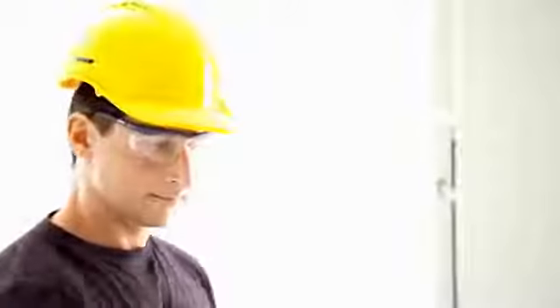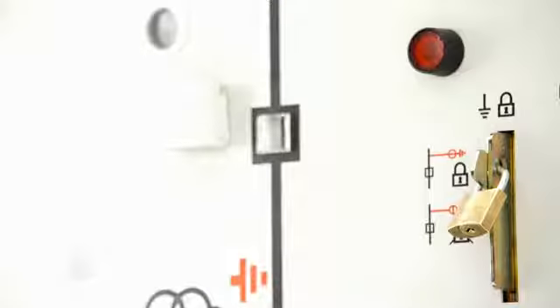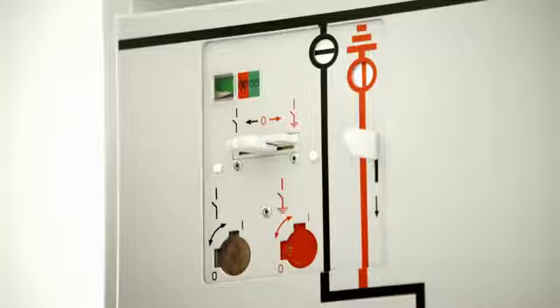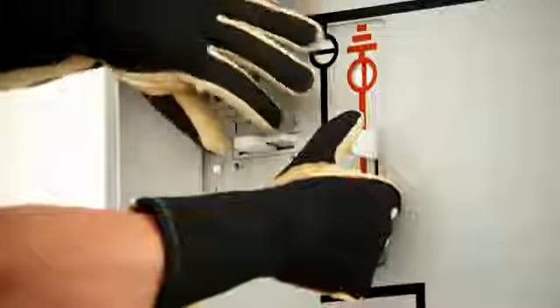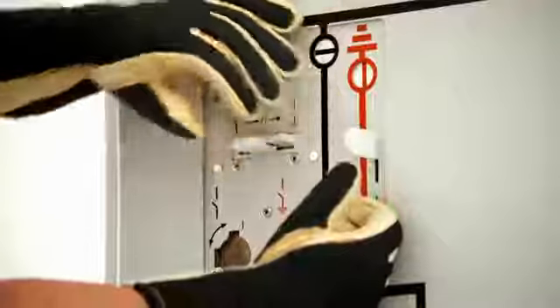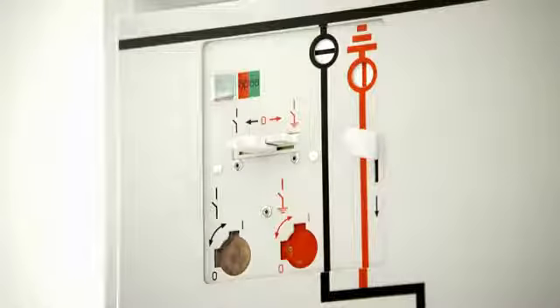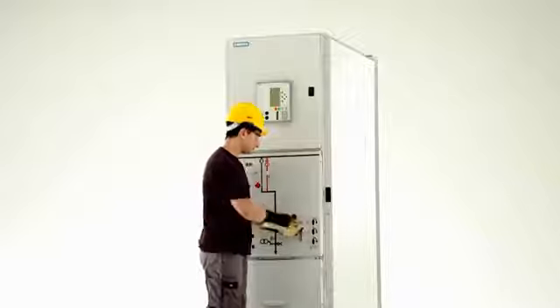De-earthing this feeder is now disabled, i.e. the circuit breaker cannot be switched to the open position. The mechanical interlocking between the circuit breaker and the three-position disconnector also makes it impossible to operate the three-position disconnector. This prevents maloperation and is a definite plus for personal safety.